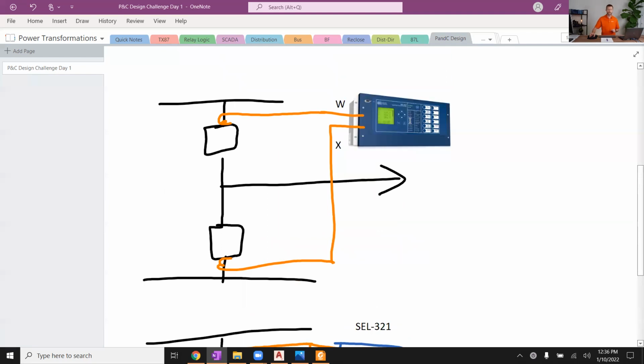Now you can do like a breaker failure scheme in your line relay where you can get the separate breaker currents and determine if one or the other breaker fails and take action. You can do independent automatic reclosing schemes on these 2 breakers. We're not going into all those schemes. I've already covered those in previous courses if you're more interested in those topics, but those are some additional advantages of separating the currents into your line relay.